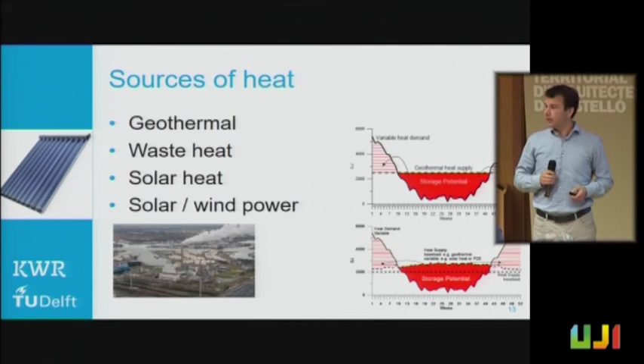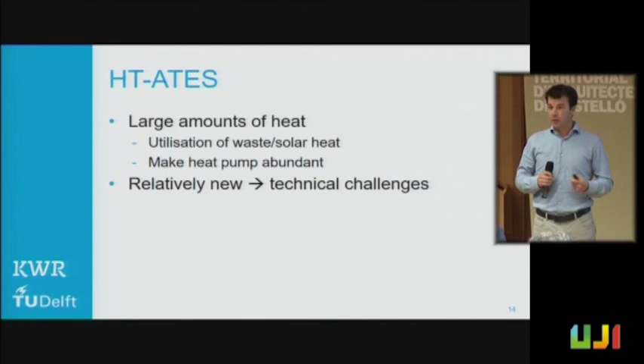This high temperature, what we call high temperature, is higher than about 30 degrees, which is currently in most European countries the limit allowed for injecting warm water. If we go to 40 or 60 degrees, we can directly supply that to buildings, so we can store much more heat in these aquifers. We can make the heat pump redundant, which is a very large benefit for the power grid as well.